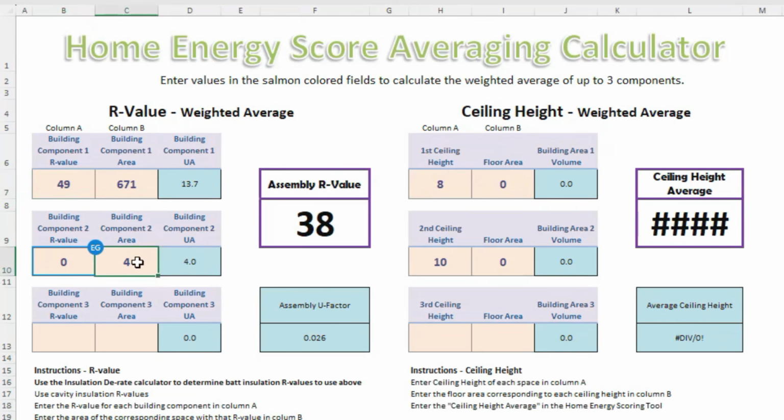So let's just, for fun, let's increase this a little bit. Let's make it even numbers. Let's say it's a 1,000 square foot attic. Let's say that right now there's no uninsulated area. It's an even R49. But let's say your remodeling company comes in, they do a bathroom for you. And let's just say your bathroom is 5 by 8. And they pull up all the insulation, 40 square feet, 960. Look what happens to your entire R value. Look what happens when the remodeler comes up and doesn't put your insulation back.